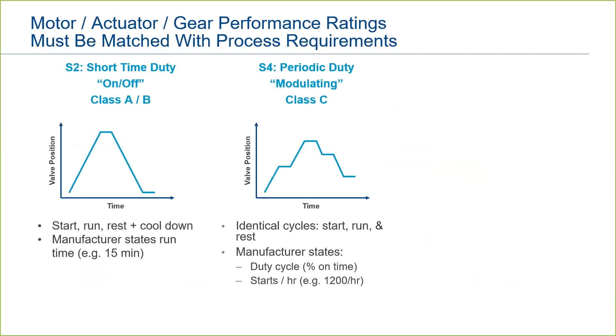Manufacturers will also state a number of starts per hour — for example, 600 starts per hour or 1,200 starts per hour. There are two types of things that are particularly tough on a motor: high temperatures and starting. Temperature stresses the insulation, and starting causes high inrush current. That is why you'll see specifications stated around run time and number of starts.